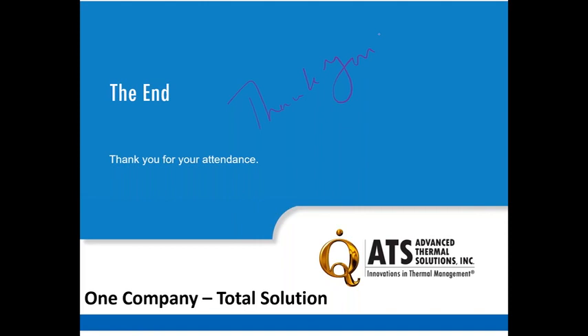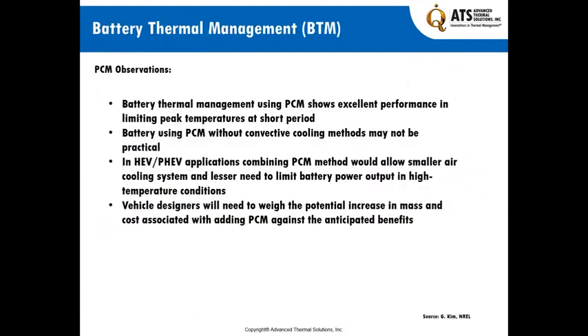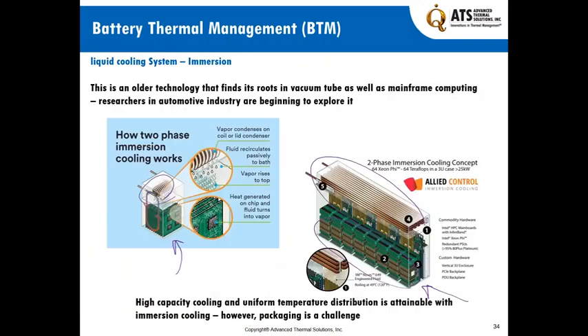The biggest challenge with two-phase immersion cooling is the same thing we've seen in the high performance computing industry, or even the vacuum tube era way back before that. The issue is packaging, thermal runaway, and making sure the cooling system—the heat exchanger I showed at the top—let me go back so I can point to it effectively.